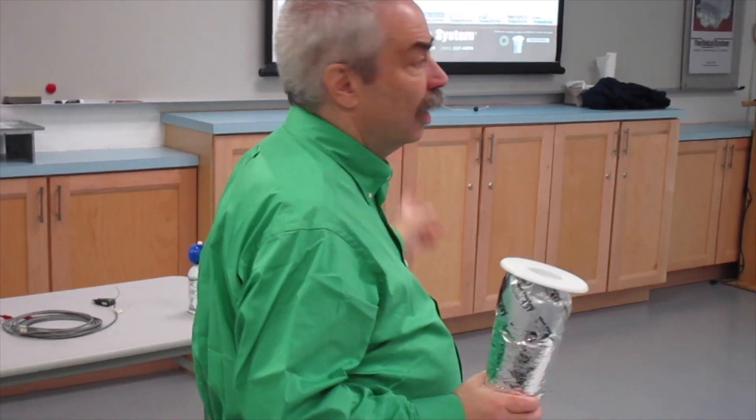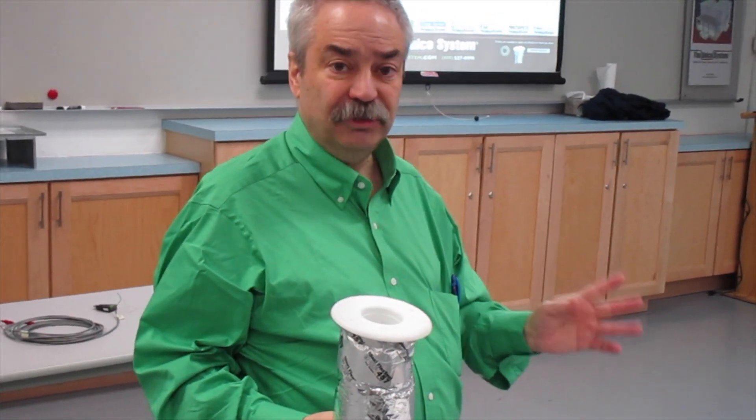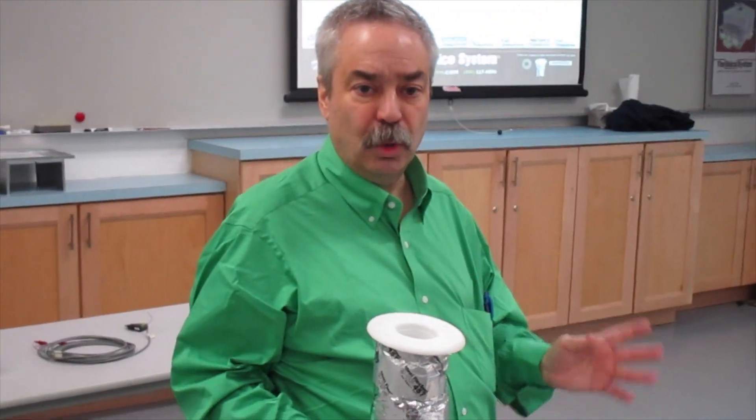The other thing is the number of outlets you put in. The biggest thing that people come back with from my Unico 101 classes is they know to put in at least six full outlets per ton. If they do that, we have about 29 decibels at the outlets.